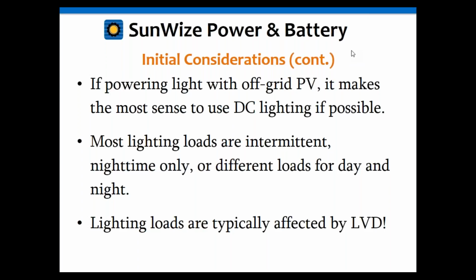Most of the lighting loads are actually going to be intermittent, generally nighttime only. However, there are some that are going to be daytime, perhaps when it comes to some type of navigational load, or I know for obstruction lighting, sometimes it might have a white light for the day and red lights at night, or vice versa, or something like that. So sometimes there are different size loads for day and night, and some loads are nighttime only, especially when it comes to street lighting and security lighting and stuff like that. So keep that in mind when you're doing your load calculations.